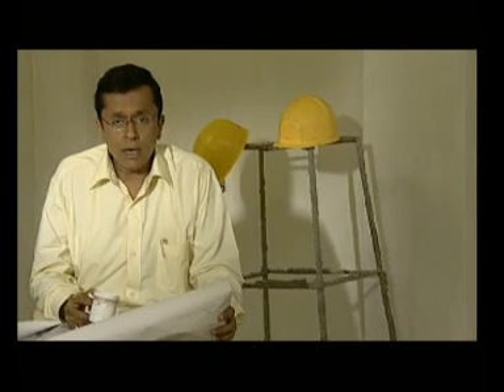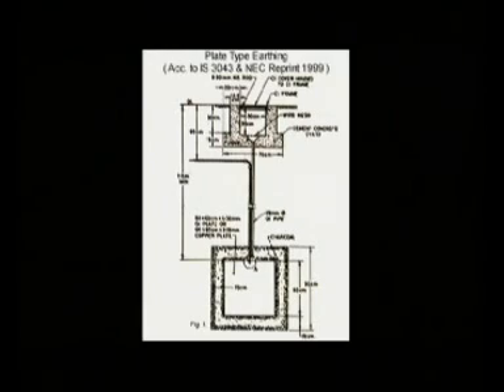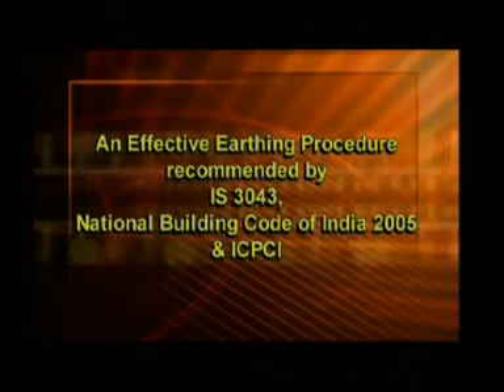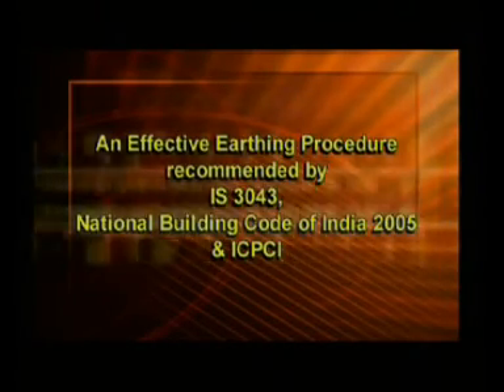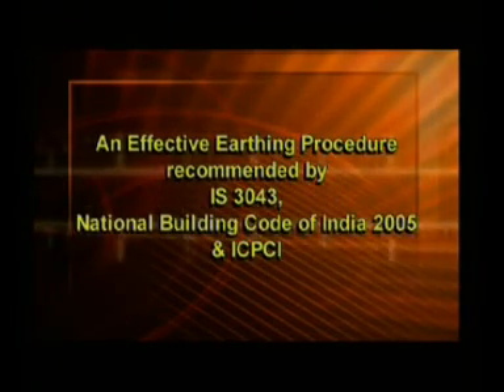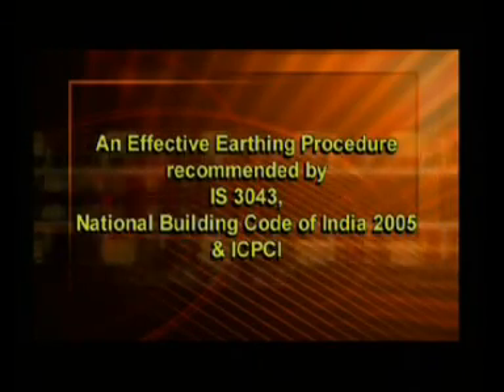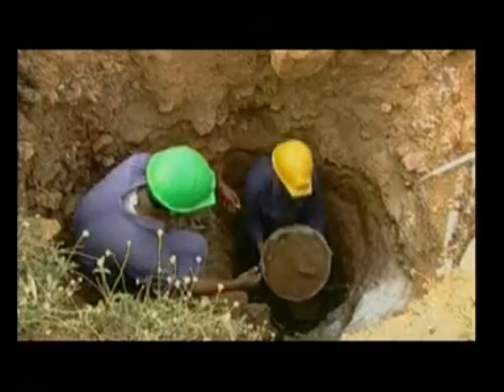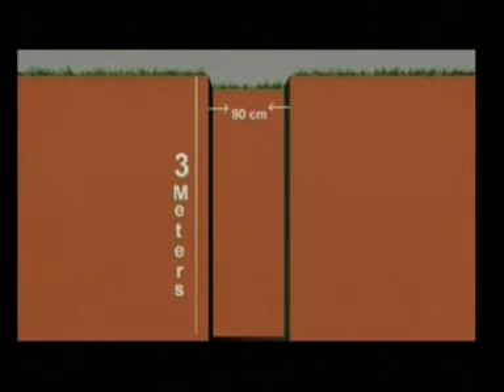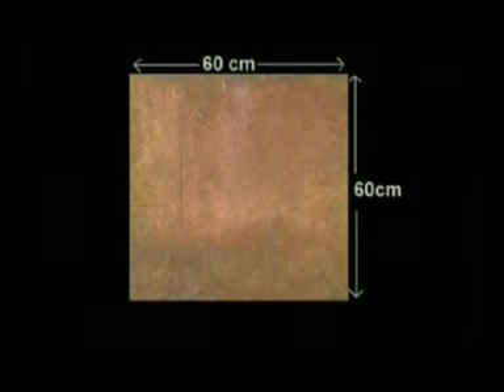Proper earthing is most essential for household wiring, but sadly it is also the most neglected. IS 3043 has laid down a code of practice for this. Let us take a look at a model of efficient earthing as suggested by the IS 3043, the National Building Code of India 2005 and the ICPCI. A pit 3 meter deep and 90 centimeters square is dug. A copper plate of 60 by 60 centimeters is placed at the bottom. This acts as an earth electrode.